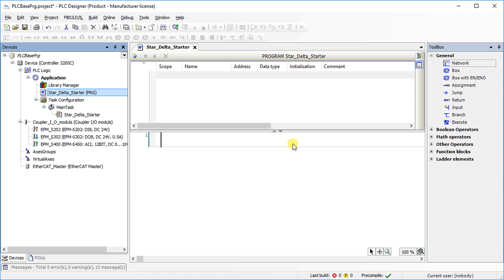We will write a logic of star delta operation of a motor for understanding the ladder writing procedure, where start push button turns on the motor using star connection and then automatically switch to delta connection using a time delay. Stop push button stops the motor.